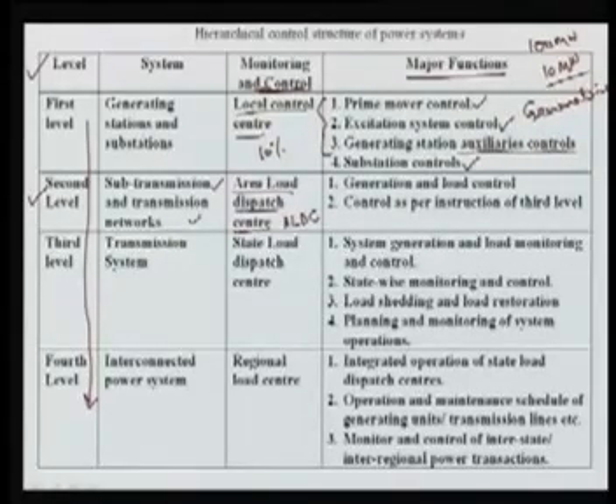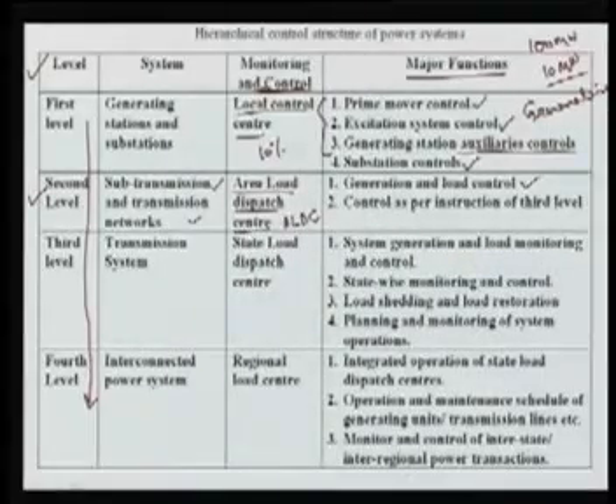So the major functions of ALDC are generation and load control. Means here we control the generation so that we can meet the demand. At the same time, in the load control, we have to go for load control as well, so that we can match generation and load together, so that we can maintain the frequency and we can operate our system smoothly.